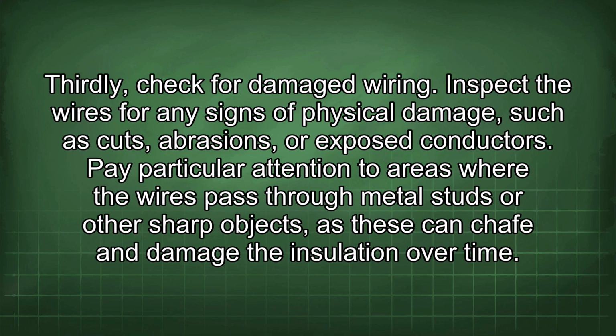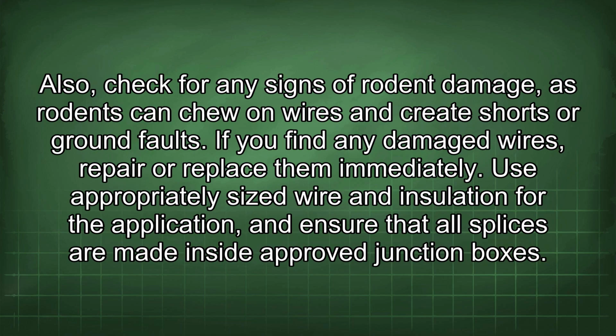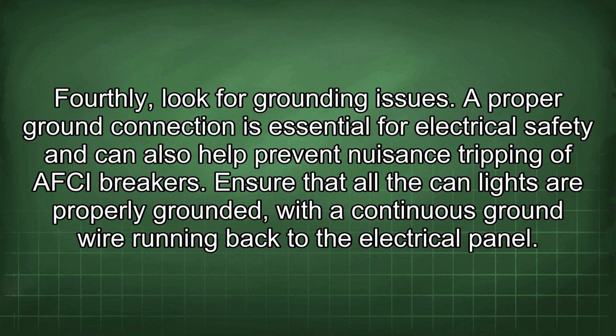Thirdly, check for damaged wiring. Inspect the wires for any signs of physical damage, such as cuts, abrasions, or exposed conductors. Pay particular attention to areas where the wires pass through metal studs or other sharp objects, as these can chafe and damage the insulation over time. Also, check for any signs of rodent damage, as rodents can chew on wires and create shorts or ground faults. If you find any damaged wires, repair or replace them immediately. Use appropriately sized wire and insulation for the application, and ensure that all splices are made inside approved junction boxes. Fourthly, look for grounding issues.